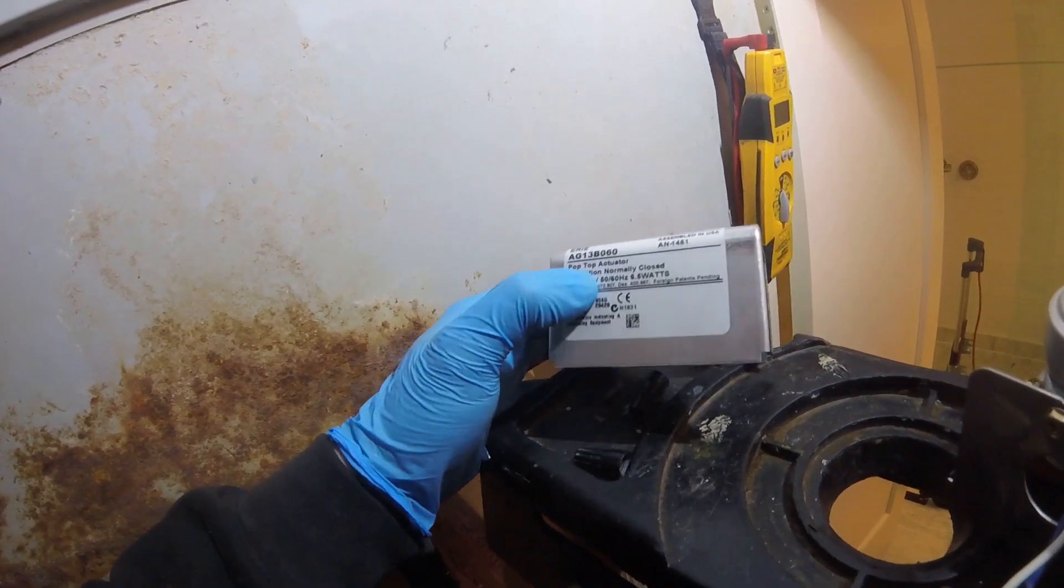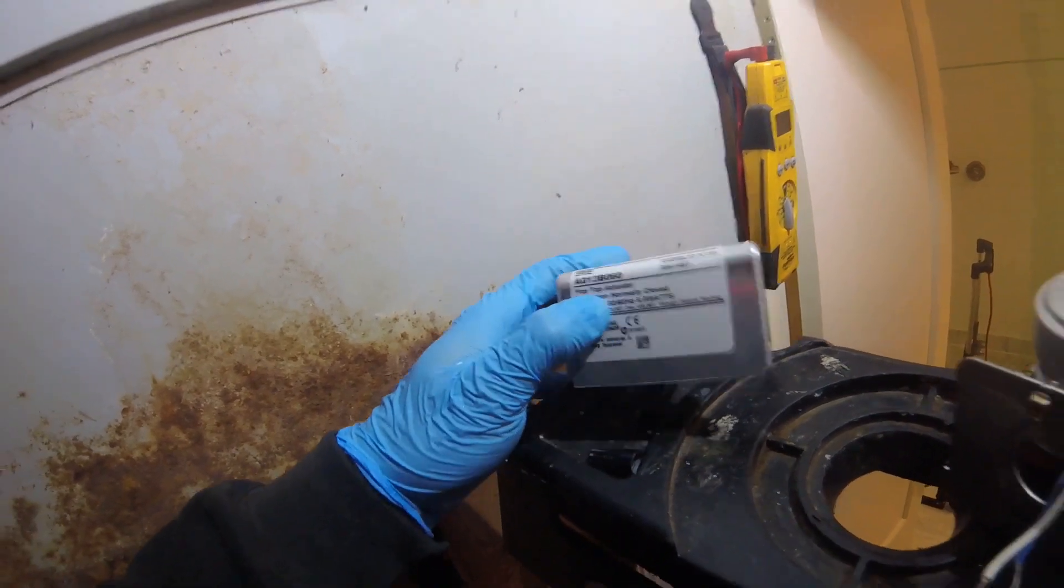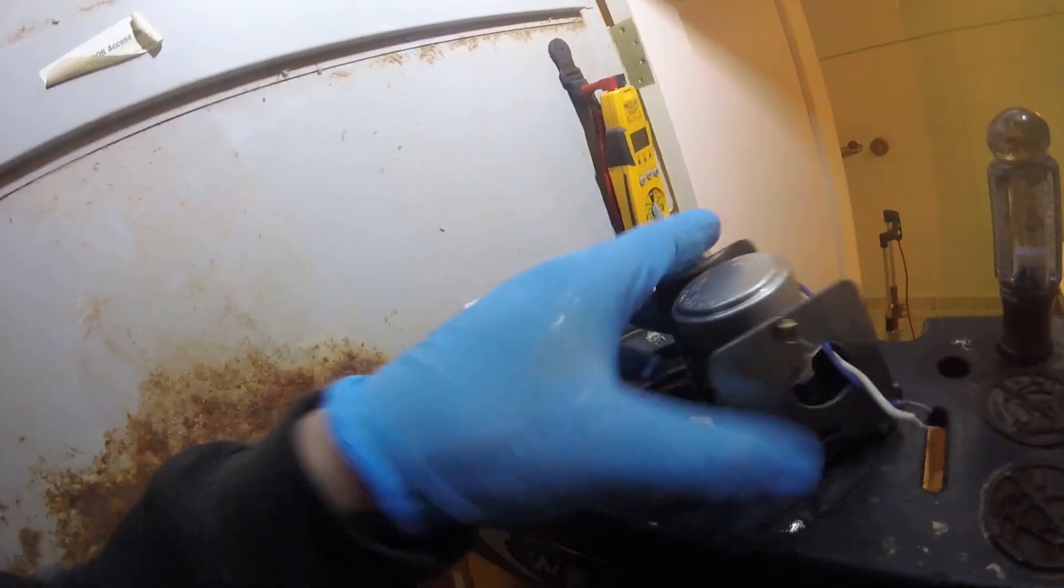I just want to see if it's normally open or closed. Right here, normally closed. So we need a normally closed 120 volt actuator. I might have one in the truck actually.